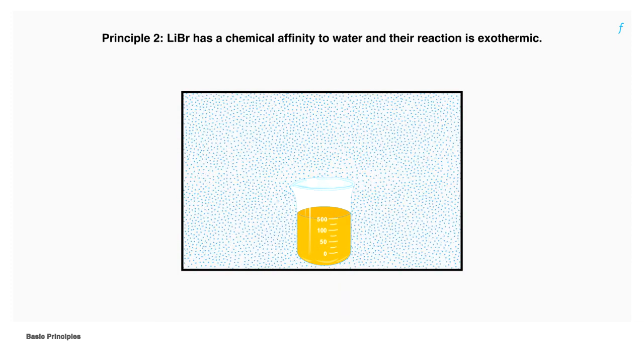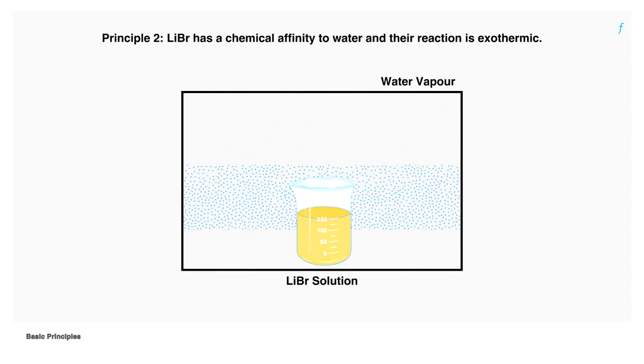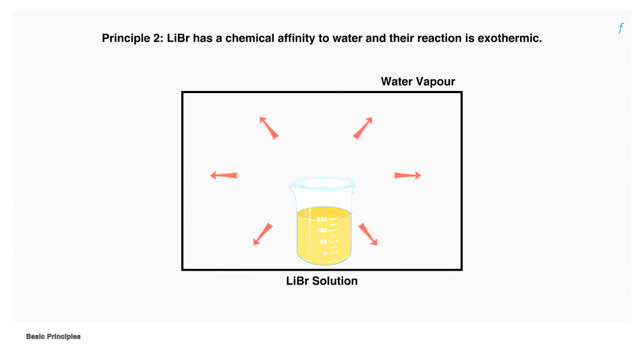Lithium bromide has a chemical affinity to water. That is, it will easily bond with water as soon as it is exposed to it. This process, that is the absorption of water vapor by lithium bromide, is exothermic. That is, it releases heat.